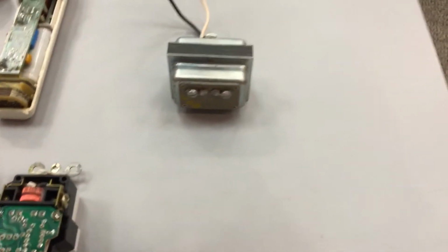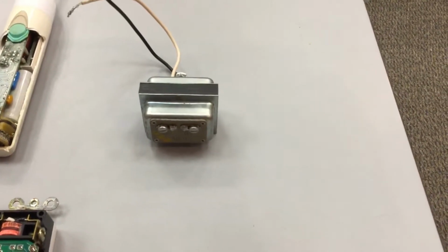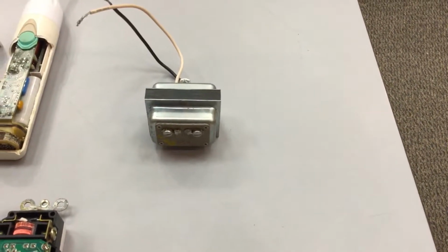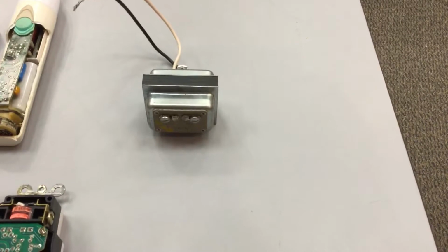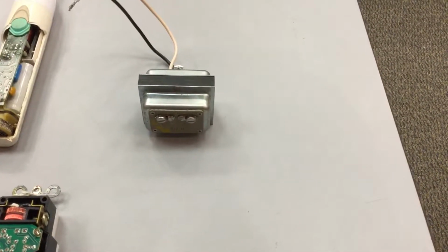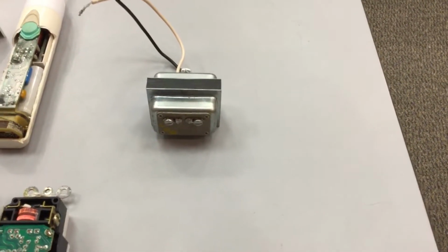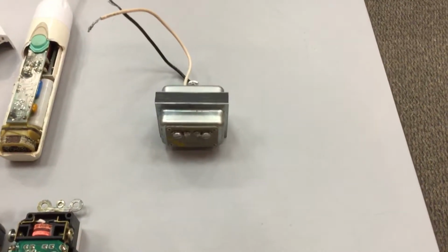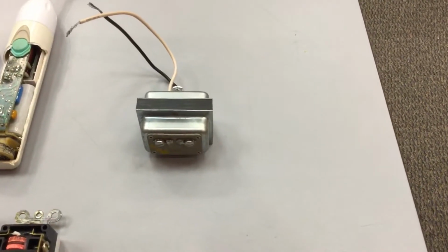This particular transformer says 10 VA, in other words 10 volt amps. They're giving you the apparent power because they have no idea what the inductance or capacitance is of the thing you're going to hook to it. So they give you apparent power and say we can handle 10 VA.